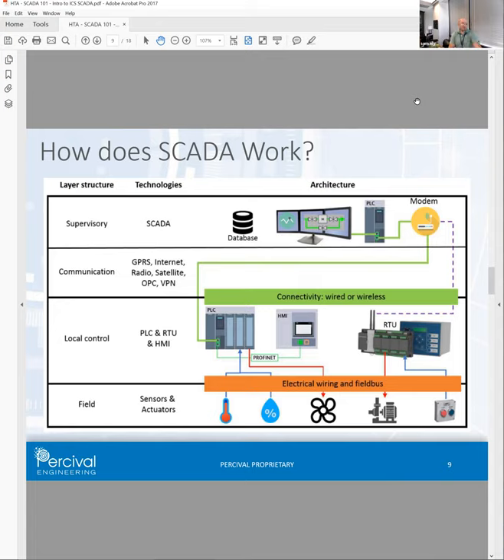So that temperature makes its way back over the PLC, and the PLC goes, okay, 72, 72, 73, alright we're getting a little close, 73, 74, oh we're over the limit, turn the air conditioner on. So the air conditioner cuts on. Now, air conditioners have multiple stages - well, some do - so it turns on the low stage first. Then it checks, are we trending back down, or do we need to turn on the high stage? In the high stage it really pumps out that cold air, so on a really hot day like we've been having here in Baltimore, that's when that second stage might kick in.